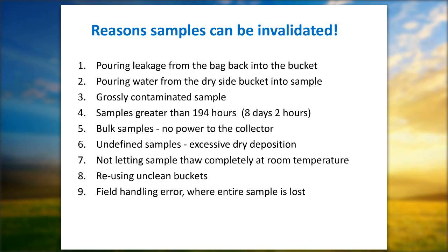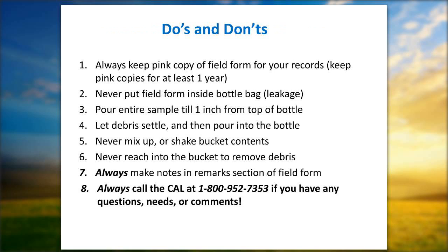And the field form is a reference point for going back and talking to an operator about, maybe, the difference. A lot of the stress is to get within the 5% between the collector and the gauge. And a lot of times when you're not within the 5%, there can be the question as to why not. We can elaborate a little bit further into the function of the equipment, what may have occurred. So keeping a field form handy to where we can use it as a reference point is very important.